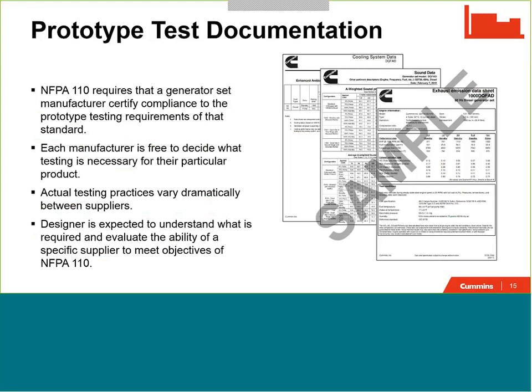So again, driving towards what you should be looking for from prototype testing is not just an indicator of compliance with NFPA 110, but you should be looking for additional testing detail, additional data or data sheets that the manufacturer can provide that indicate the additional prototype tests that have been conducted on that particular product.